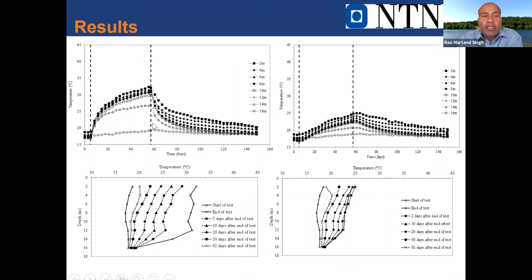These are the borehole temperatures. The ground temperature responded, but it was much lower than the pile temperature. The pile temperature was around 40 degrees, here it was 30. One borehole is 0.5 meter away, another is 2 meters, and that one has a much lower temperature rise. This also gives us an idea of how far we should space the piles.